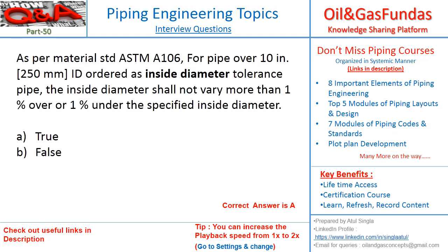This is a true statement. This is one of the important clauses mentioned in ASTM A106 regarding inside diameter tolerances. Whenever we order a pipe with size more than 10 inch, the manufacturer may have some discrepancy in size. The accepted variation is up to 1% over and 1% under the specified inside diameter, since it is impossible to maintain uniformly the same ID throughout the pipe. This clause gives some provision to accept variation from the manufacturer.